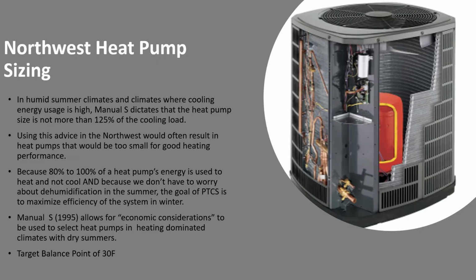Northwest heat pump sizing, we really get a break here. In humid summer climates and climates where cooling usage is high, Manual S dictates that the heat pump size not be more than 125% of the cooling load. The good news, when we get hot, we get dry. Manual J and Manual S, as they should be, are quite concerned about dehumidification in humid climates. When we get hot, we're not a humid climate.